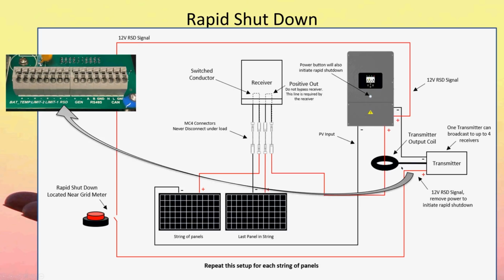What we basically do is we put in the negative side, I'm sorry, the negative side to the rapid shutdown transmitter, and the positive side goes to a rapid shutdown button out externally, and then comes back and loops back into the Sol Ark. So I can either hit this rapid shutdown button externally, and it will shut down the PV array, or I can turn off the on-off button on the system, and it will also shut down the transmitter.